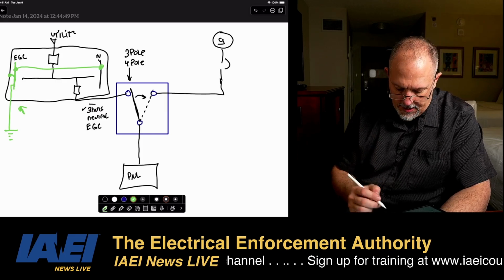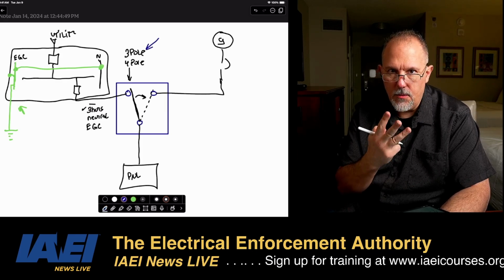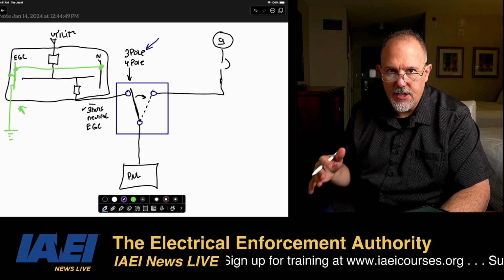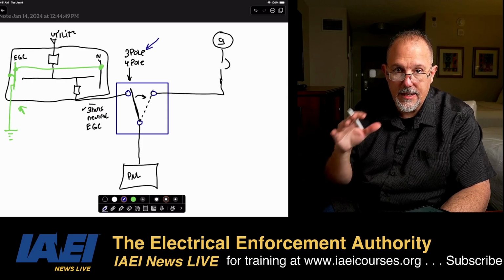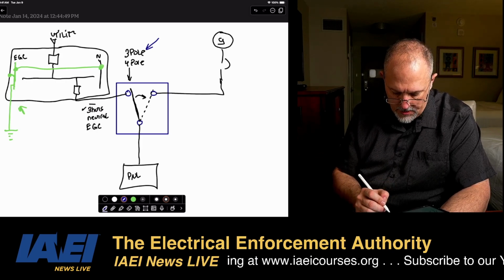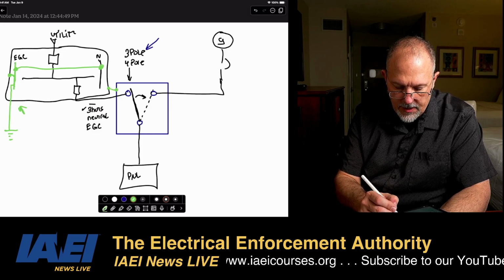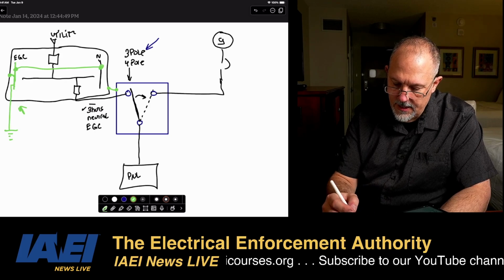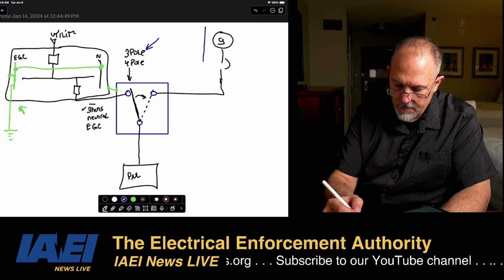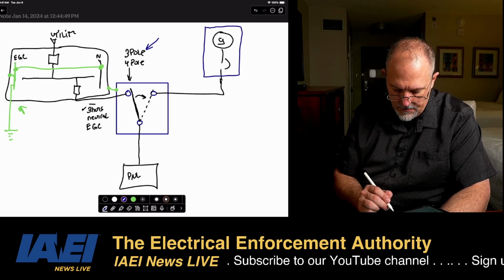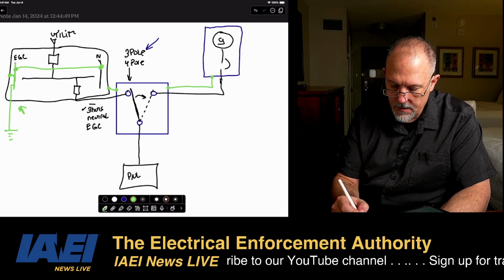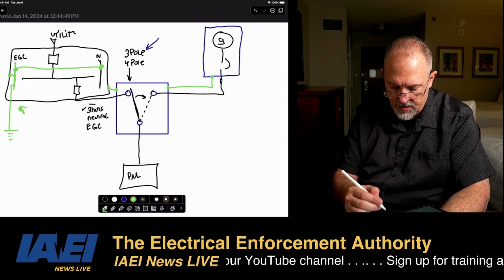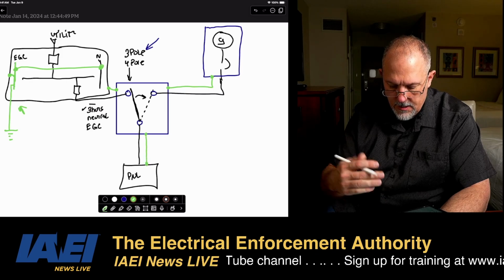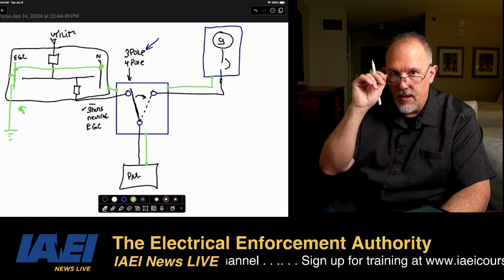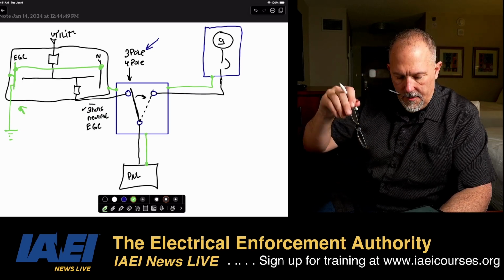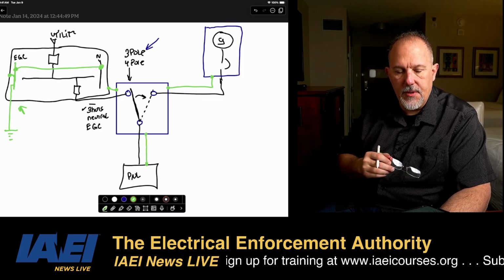If I'm only switching 3 poles, if I look back at the definition, it says everything has to be separate except for the equipment grounding. So let's just draw the equipment grounding. I know that I have a bond going between that enclosure and that enclosure. And let's say that this generator, this is all together. I am bonded. I bond the generator equipment with the transfer switch, and then I'm bonding the downstream panels, and all of my bonding has to occur as per Article 250. So all of my bonding is consistent to all of the different pieces of equipment.